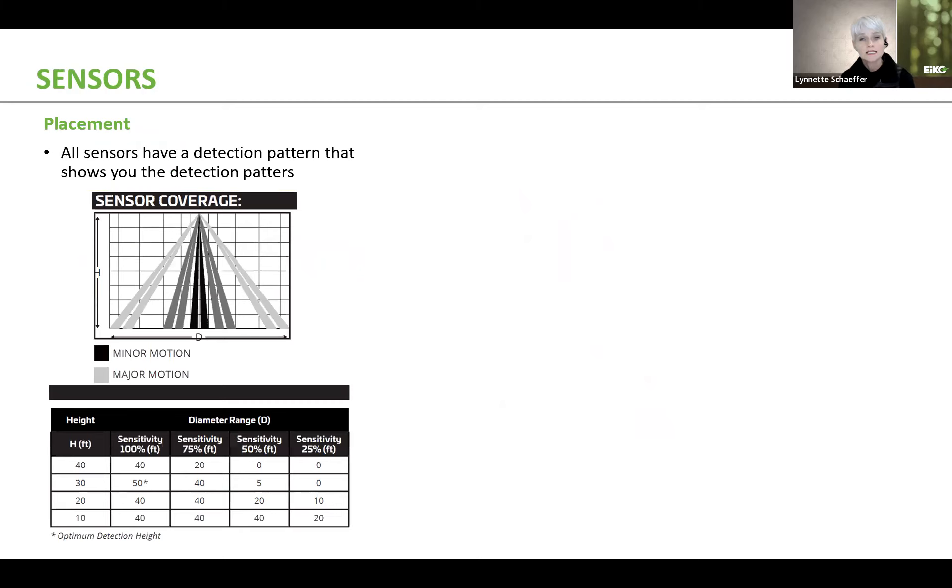Now, when it comes to sensors, something very important to consider is not only the technology, meaning do you need PIR, do you need microwave, but also the placement. This is probably almost one of the most important things outside the PIR and microwave. For this reason, all sensors have a detection pattern, which shows the coverage of the sensor based on the various sensitivity levels. If in fact you can set the sensitivity, you may actually find a sensor that does not give you the ability to set the sensitivity. In that case, it will still give you a detection pattern. It's usually always on every single spec sheet for any type of sensor.